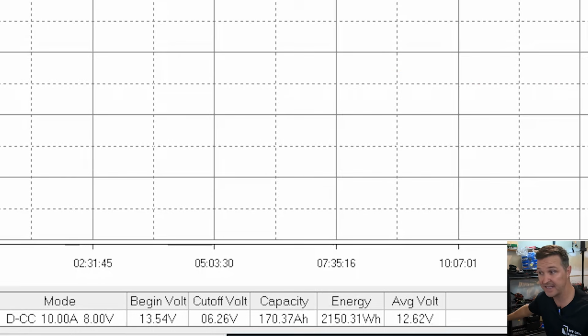When it comes to the capacity of the battery, we are looking at 170.37 amp hours, which is pretty good - about 3% higher than the rated capacity, I believe. As long as it's over 165, I'm fine with that.